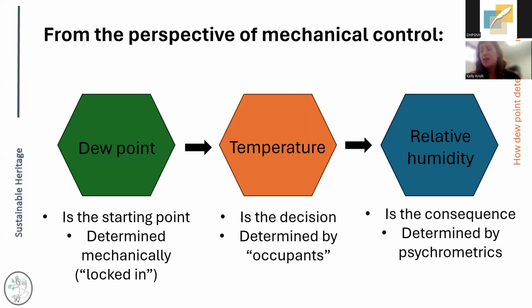The next decision is usually about temperature, and it's usually driven by, as I said, occupants. It's not always the collection. Often there will be either staff, or if we're talking about a public space, visitors, with a certain range of temperatures that's acceptable. And then relative humidity is that final consequence. It's what results from those temperature decisions. We'll talk a little bit more about that when we get to how it can determine set points.